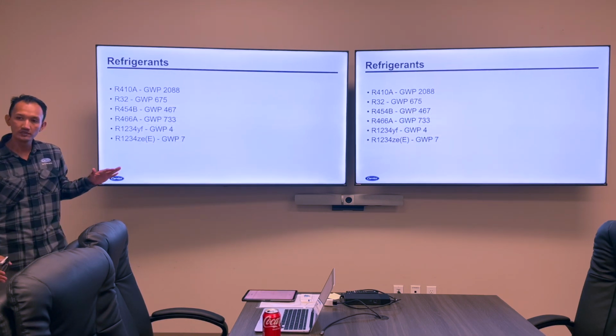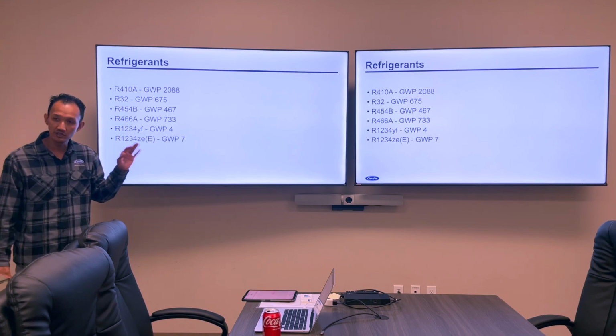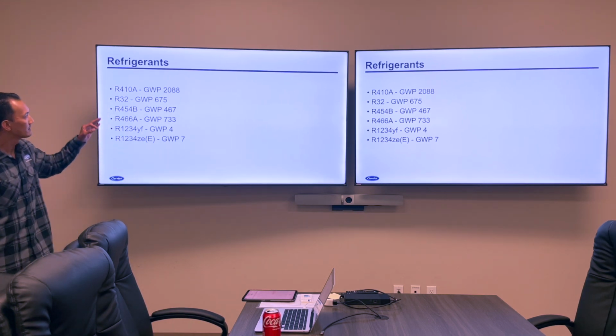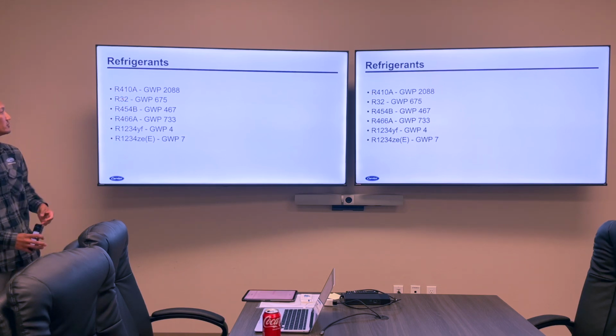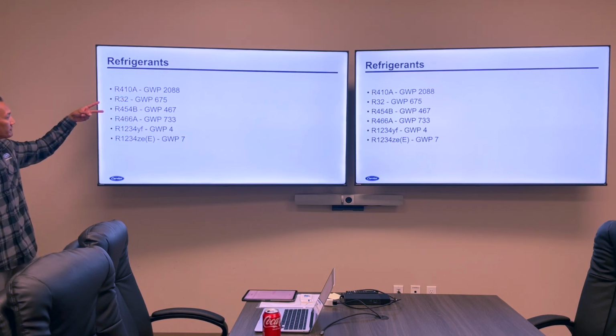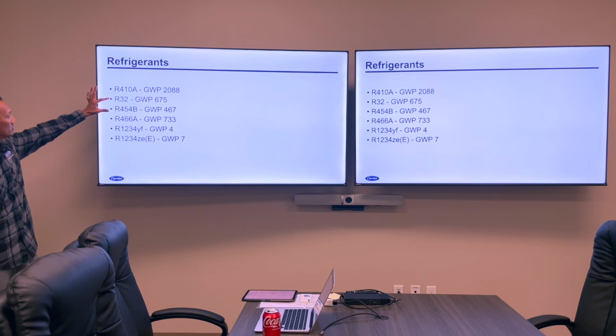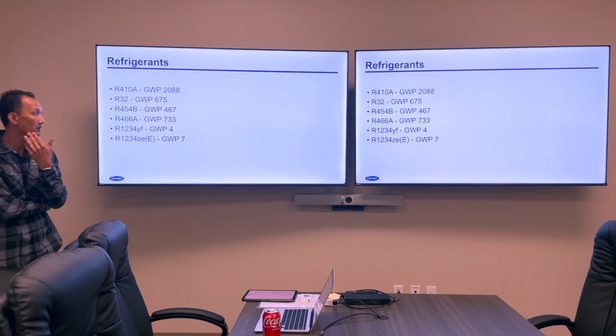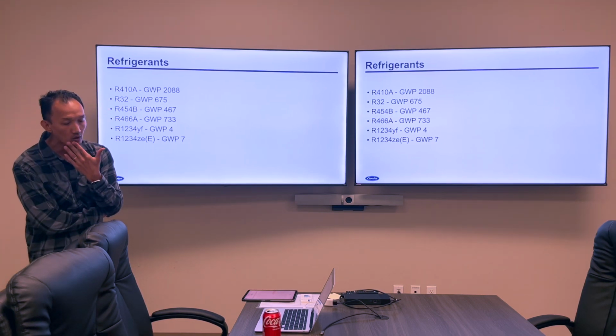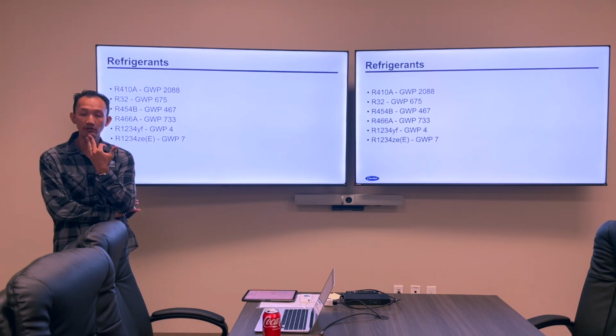Here are some common refrigerants that are being used and their GWP. R410A has a GWP of over 2,000. The majority of VRF manufacturers are using the next two refrigerants, R32 and R454B. I know a lot of our competition is using R32.